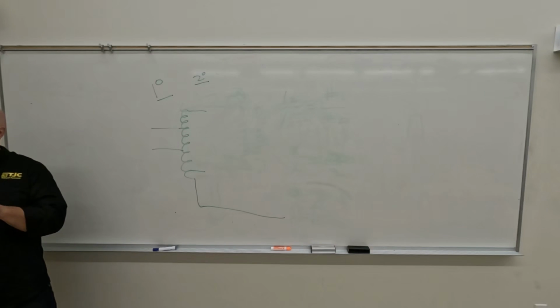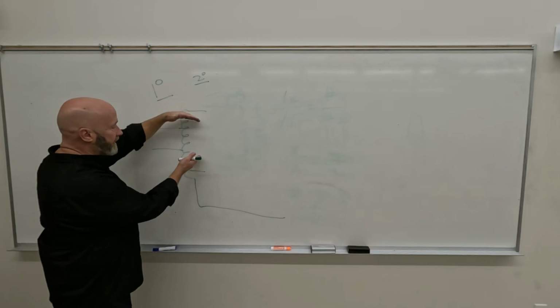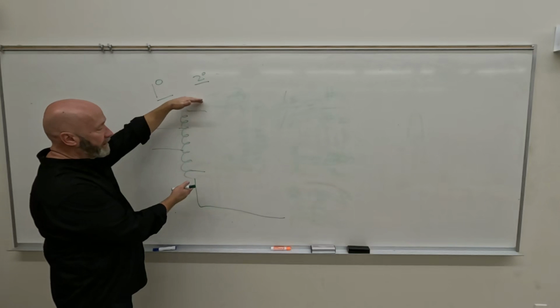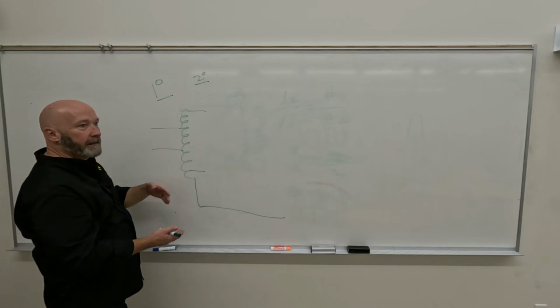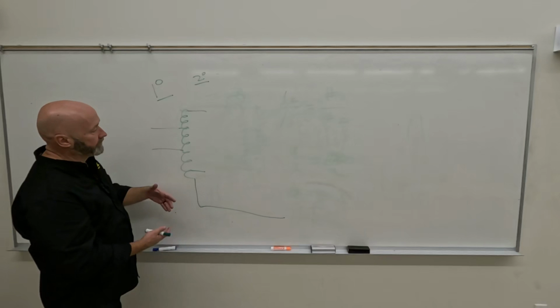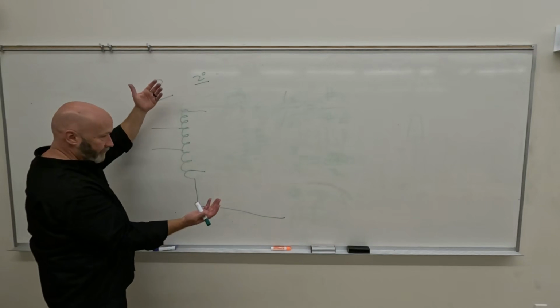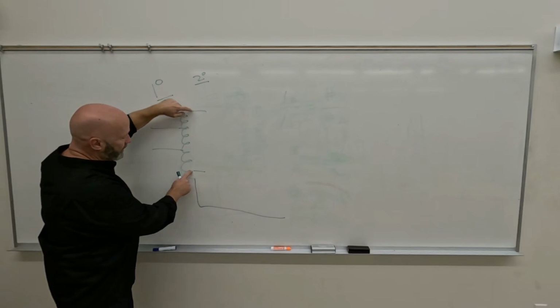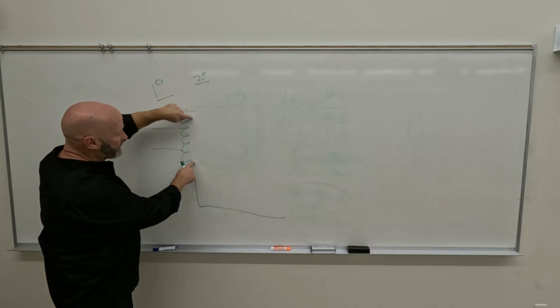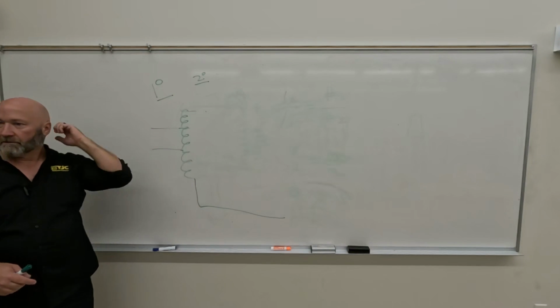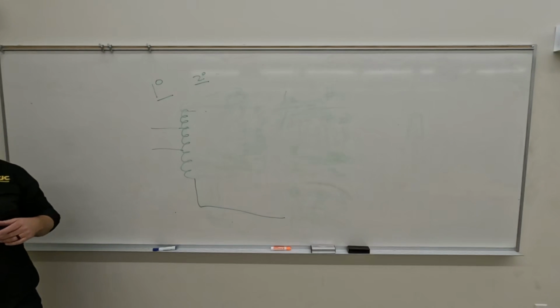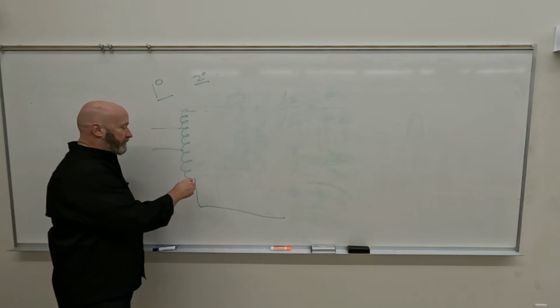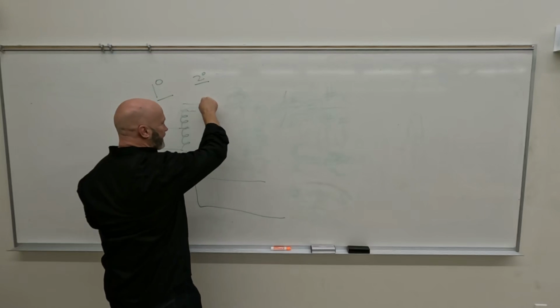So when you adjust your KVP, you push the buttons on your control panel, what you're actually doing is adjusting the contacts on the secondary side of the auto transformer, the rheostat, the KVP selector, the variable resistor—all those things. Regardless of what you want to call it, you're adjusting where these two things come in contact on the secondary side of this, increasing or decreasing your voltage at this point. But we still call it a KVP selector. Why do we call it a KVP selector? Well, what's the second thing it goes into?